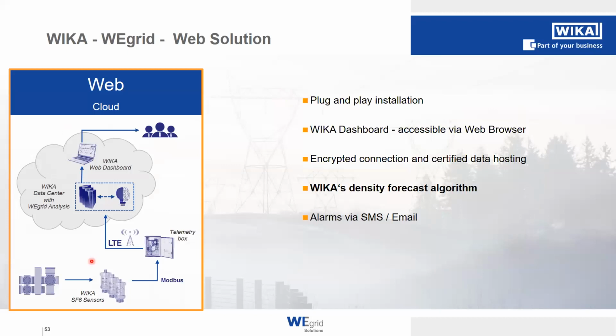So let's take a look at the different solutions that we have and that I already mentioned before. First of all, we have the web solution. So let's take a look at the graph on the left side down here. We have our GIS, the operator is running the GIS, and the GIS is equipped with the WEGrid SF6 sensors, which are then connected via a Modbus line to the telemetry box. And in this web solution, the gateway in the telemetry box is using a mobile internet connection to send the data to our encrypted and certified data hosting center from WEGrid.